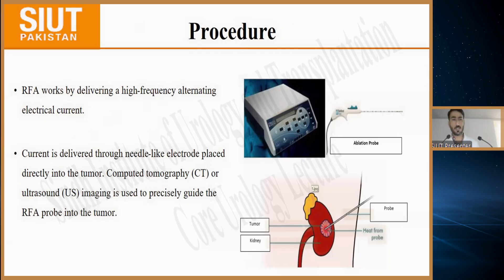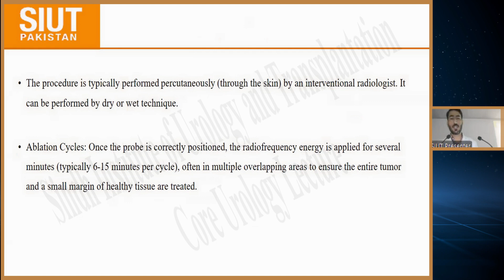Ablation cycles. Once the probe is correctly positioned, the radiofrequency energy is applied for several minutes, typically 6 to 15 minutes per cycle, often in multiple overlapping areas to ensure the entire tumor and a small margin of healthy tissue are treated. In radiofrequency ablation, the terms dry technique and wet technique refer to different methods of managing heat and impedance at the interface of the electrode. Heat management: in dry technique, no active cooling, heat builds rapidly. In wet technique, use internal cooling or saline infusion to manage heat.